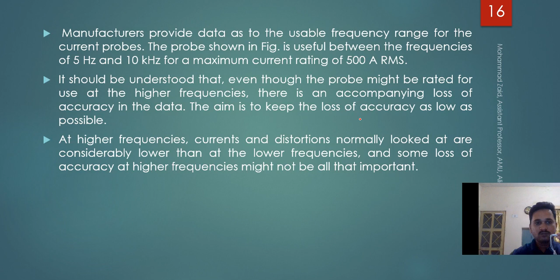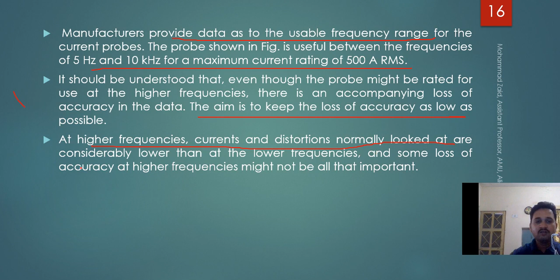Okay, so manufacturers provide data for the usable frequency range of a current probe. The current probe in the previous figure has a range between 5 hertz and 10 kilohertz using a current rating of 500 amperes. But we should keep the accuracy. The aim is to keep the loss of accuracy as low as possible. Some loss of accuracy will always happen at higher frequencies. That is the idea. At higher frequencies, current distortions normally looked at are considerably lower.